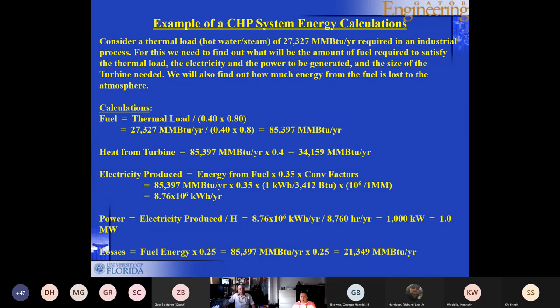The electricity produced is going to be 35% of that number, which is 85,000. You have to have the conversion factors, of course, to convert it into kilowatt hour per year. You end up with 8.76 times 10 to the 6 kilowatt hour per year. And then the power in megawatt that would be required would be the electricity produced divided by the number of hours, so that you can get it in megawatt. And you will end up with 1 megawatt. We just got lucky on that.